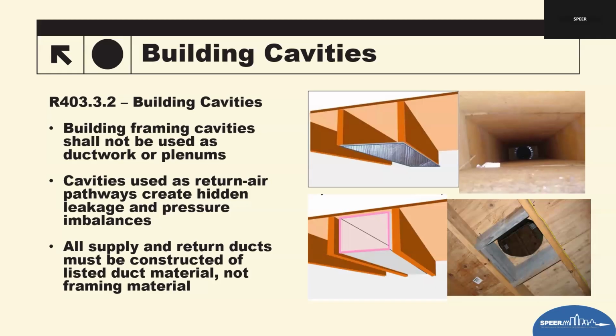The reason is that cavities used as return air pathways or supplies create hidden leakage, and pressure imbalances are now created within the system because air is coming from a different place. So when a wall or floor cavity is used as a return, it's almost impossible to air seal. We see pictures here, and if you put mastic on that, that's great. It's probably going to be a snapshot in time, and then as those things start to move, swell, dry, and people walk on it, it just starts cracking. Now we've got uncontrolled leaks inside of that.